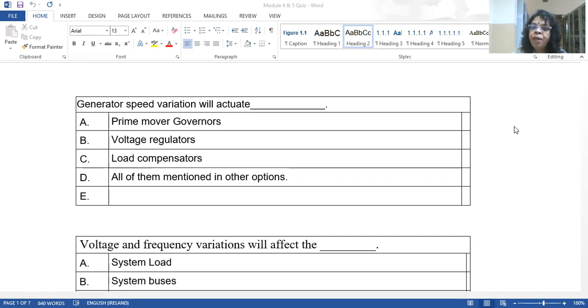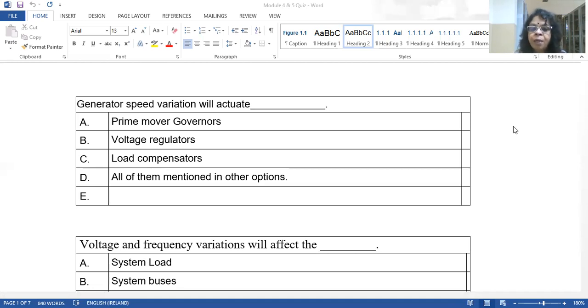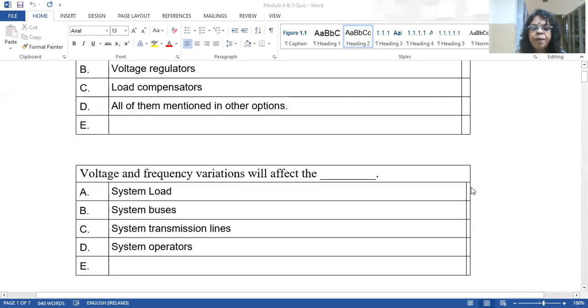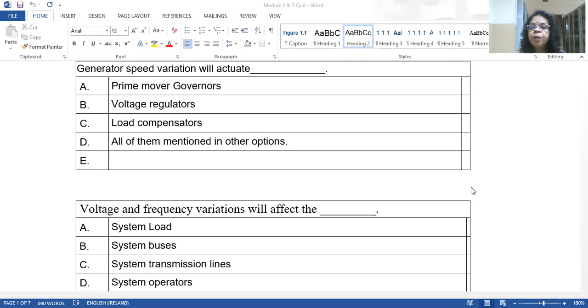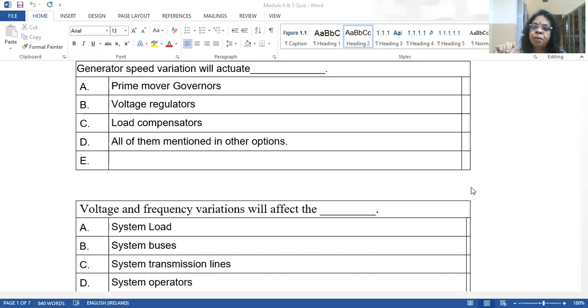This is the entire concept studied in stability and load frequency control. Therefore, any generator speed variation will actuate the prime mover governors — that is the correct answer. Voltage regulation is done by automatic voltage regulators based on terminal voltage. Load compensators are for power factor correction or balancing an unbalanced system. The correct answer is prime mover governors.